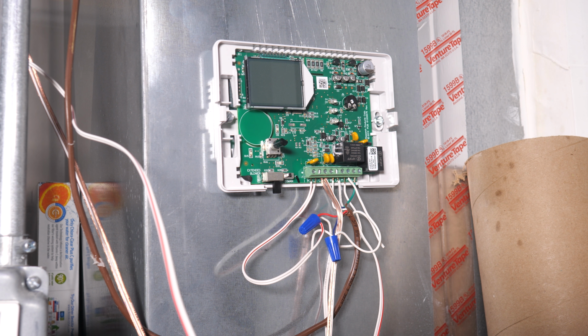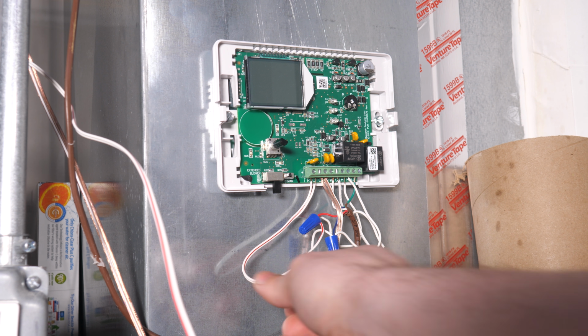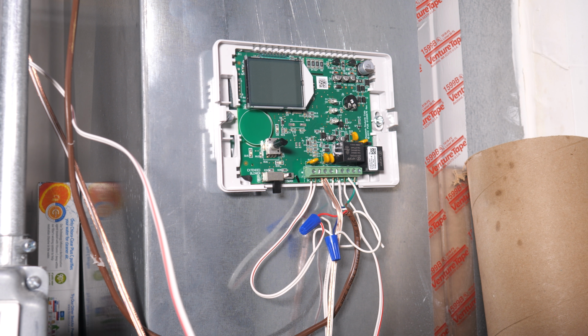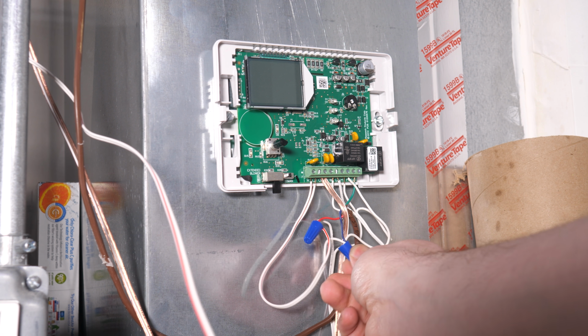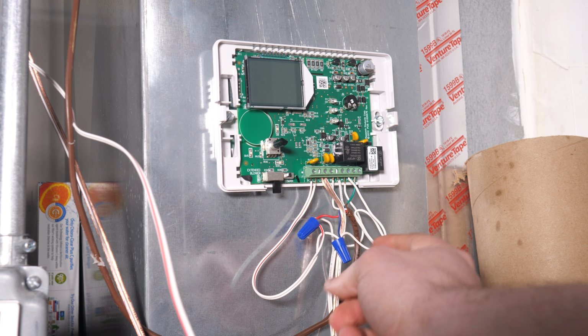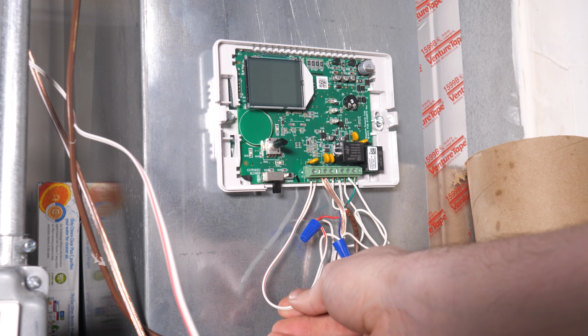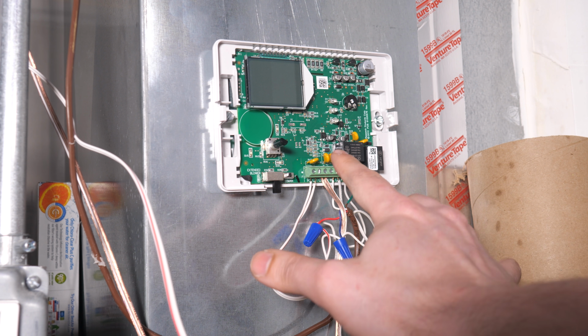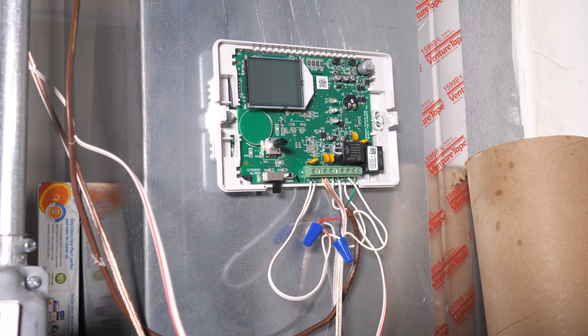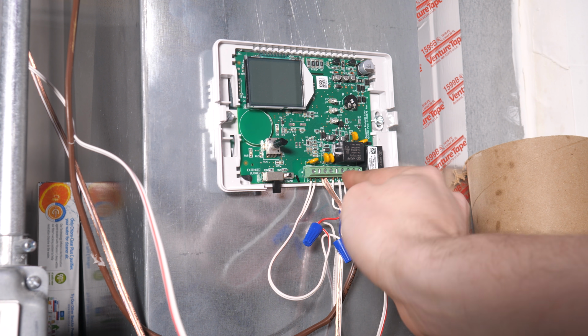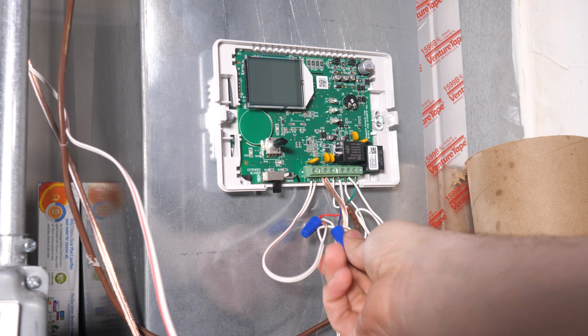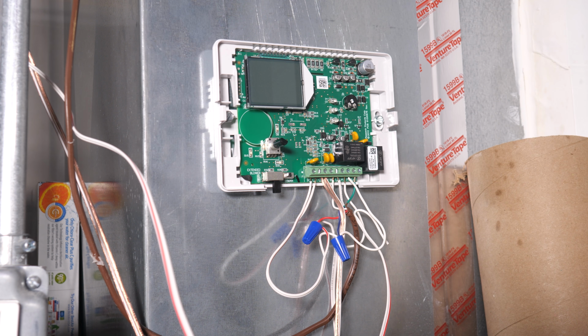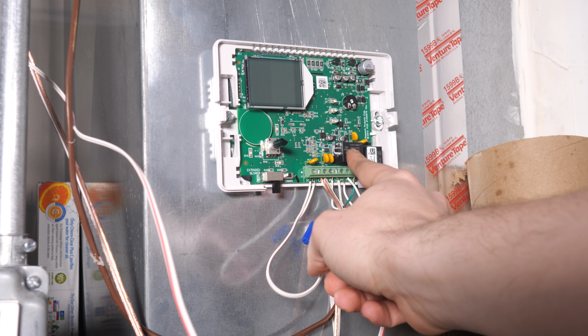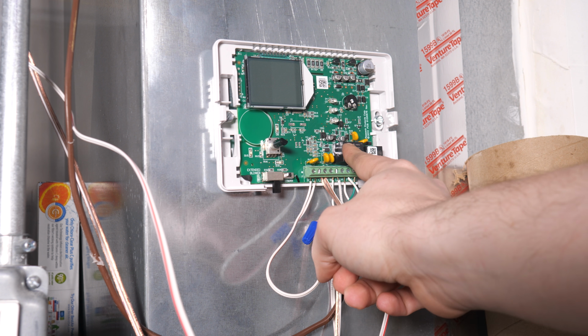Okay, my modifications are complete. Now this is going to look very confusing because almost none of these wire colors are correct. I'm actually using garage door opener sensor wire. Yeah, but it should work. Basically, I now have red and blues, this is 24 volts and common, taken off of the input, and then I have a separate lead for them. So now, this thing and the humidifier are wired in parallel, but the humidifier's return is landing on one of the H terminals, and then the other H terminal is coming back to this common point. So basically, the humidifier would run all the time if this relay is closed, but when the relay is open, it shouldn't run.